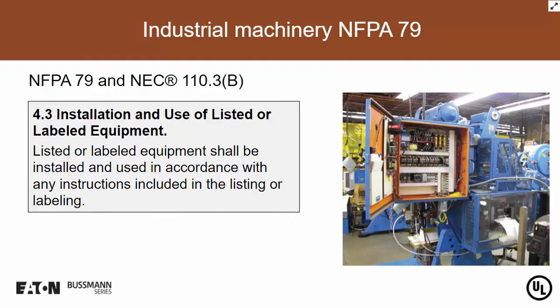Another requirement that's very important is in paragraph 4.3 in NFPA 79, which deals with installation and use of listed or labeled equipment. This is also covered in Article 110 of the NEC. Listed and labeled equipment shall be installed and used in accordance with any instructions included in the listing or labeling. And that's very important because you'll see a lot of requirements in 79 and, more importantly, in the NEC where a listed piece of equipment or a listed product is necessary or must be provided in order to comply with a requirement. But beyond just using a listed product to determine code compliance, you must also make certain that any installation instructions, any kind of warning information, any information that's provided with that product, that's part of the listing and labeling.